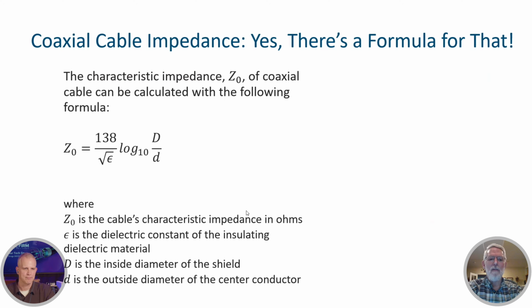There's the formula you can use to calculate the impedance of coaxial cable, with some numbers here. There's the ratio of D to d we talked about, and the square root of the dielectric constant of the insulating material. This tells you that if this ratio changes — meaning if you dent your coax, kink it, or overbend it — you're changing that ratio. And if the dielectric constant changes, think of water getting into the dielectric.